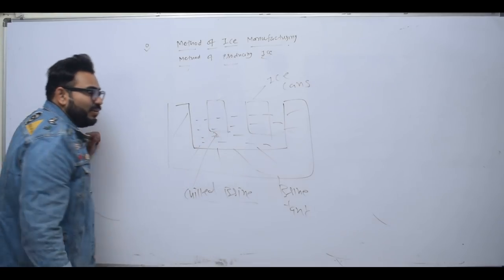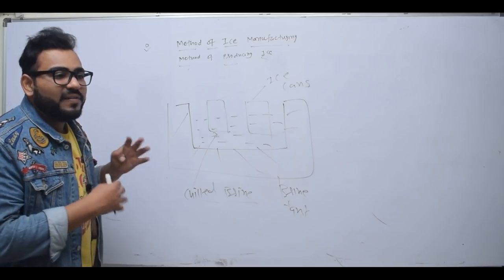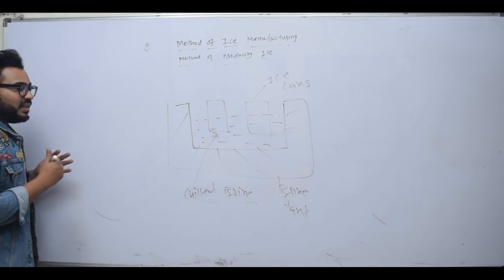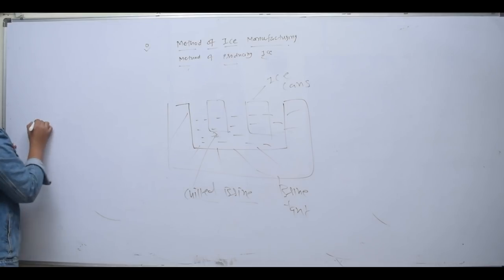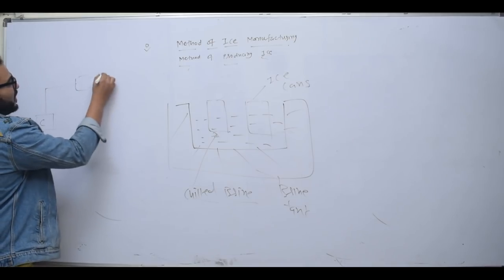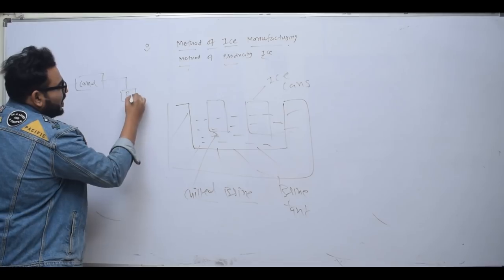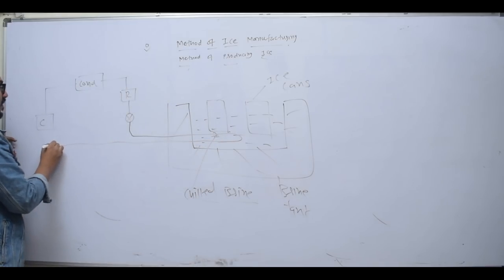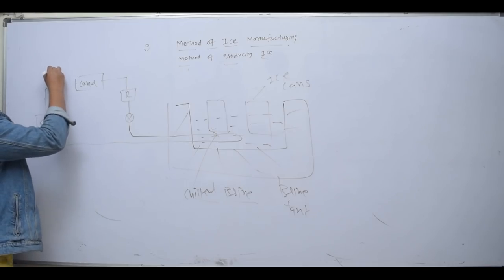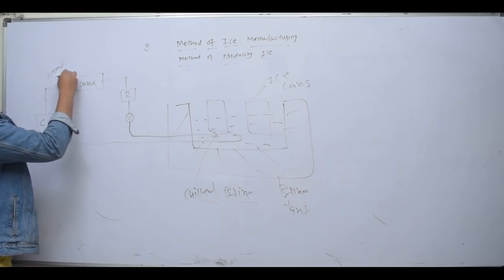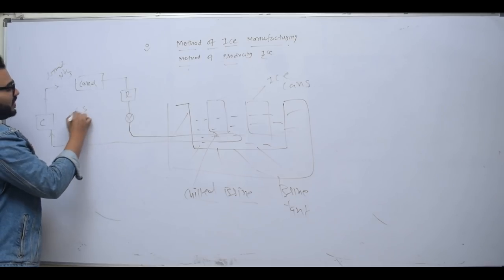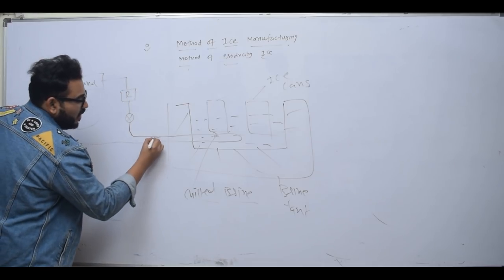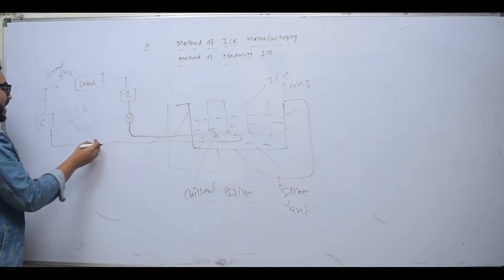So the brine needs cooling. For the brine to absorb heat and make ice, we use a vapor compression system. The system has a compressor, condenser, receiver, and expansion valve. Ammonia is used as the refrigerant. The vapor compression system with ammonia refrigerant will come to the brine tank and absorb heat from the brine.